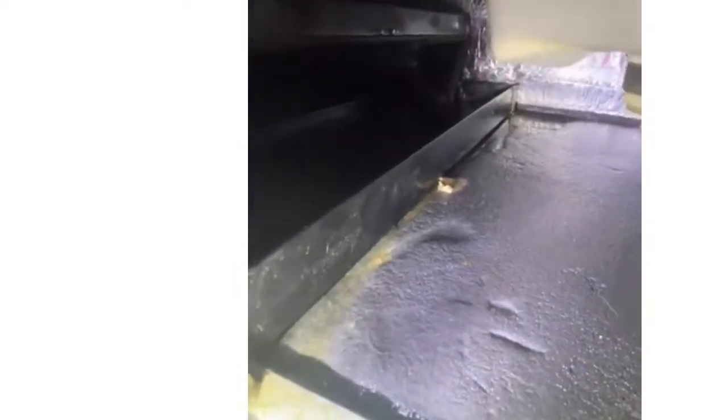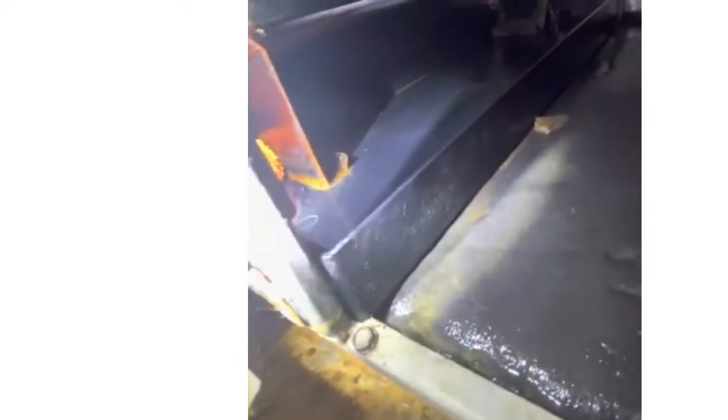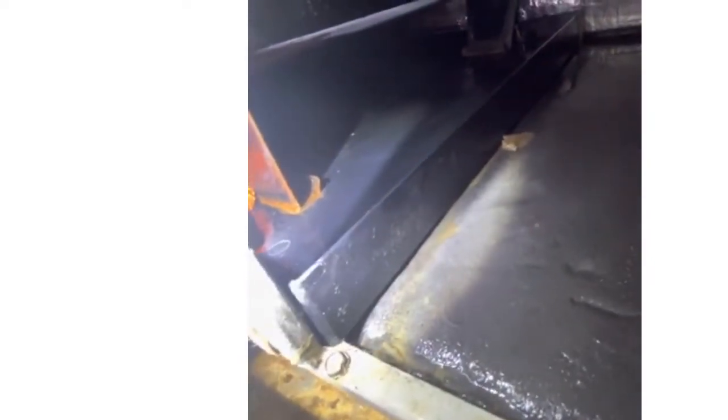So in today's lesson, we're going to look at why units get wet. This has already been relined and it's still getting wet. I dried out the pan, did not see any cracks. I took several pictures. I added water. It does look like water comes out of the little holes where the screws go in, but I don't know if that's from the pressure of the water in the pan pushing down the wet lining.